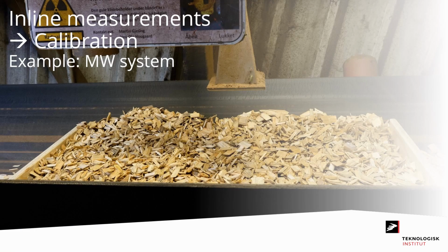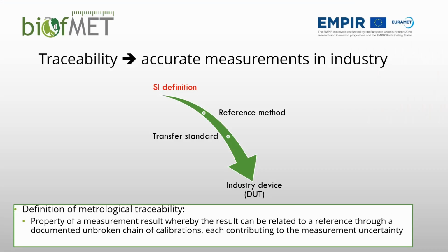The example we're going to look at is a microwave system. This is shown here, with some test sample material below. We want to make traceable water mass fraction measurements. So let's just remind ourselves that metrological traceability is a property of a measurement result whereby the result can be related to a reference through a documented unbroken chain of calibrations, each contributing to the measurement uncertainty.